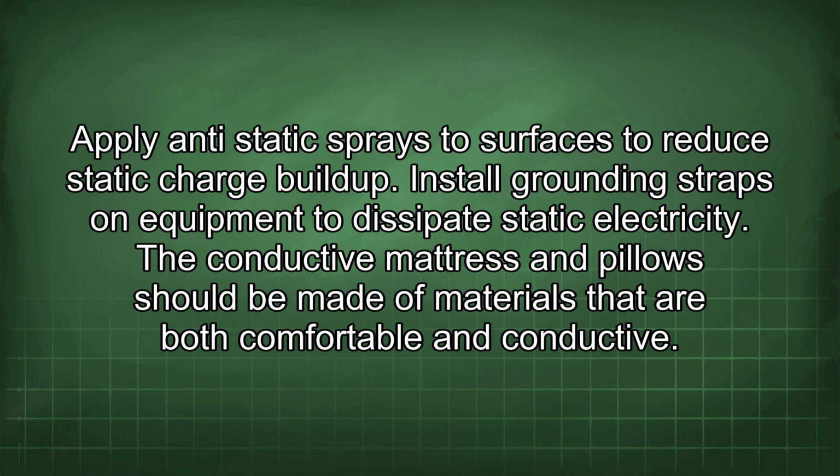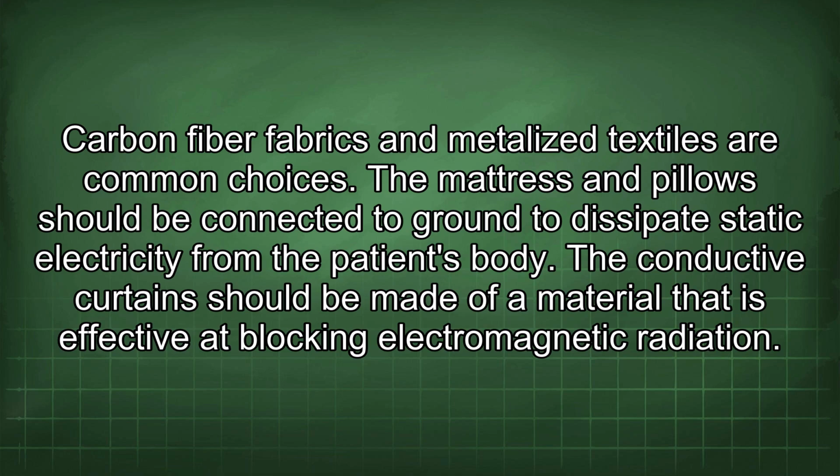The conductive mattress and pillows should be made of materials that are both comfortable and conductive. Carbon fiber fabrics and metallized textiles are common choices. The mattress and pillows should be connected to ground to dissipate static electricity from the patient's body.